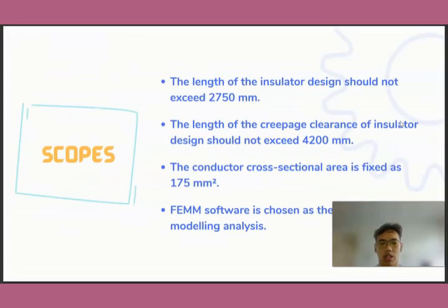Next, for the scope in this project, the length of the insulator design should not exceed 2750 mm. Second, the length of the creepage clearance of the insulator design should not exceed 4200 mm. Third, the conductor cross-sectional area is fixed as 175 mm square. Fourth, we use the FEMM software as the tool for the modeling analysis.